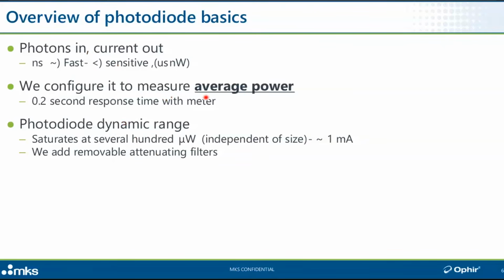Oh, I skipped over one small point. I'll just mention that briefly. We configure these photodiodes, even though they certainly are fast enough to measure energy per pulse. And as I mentioned, we do often employ photodiodes in energy per pulse sensors. But usually we're talking about power measurement.